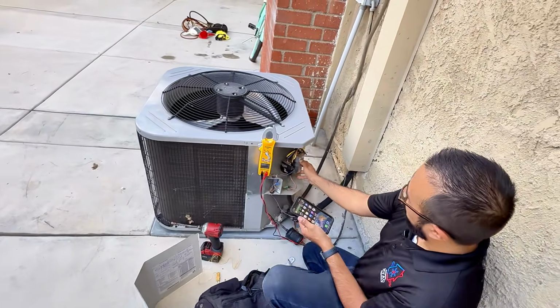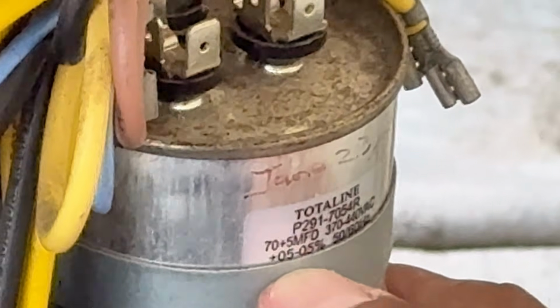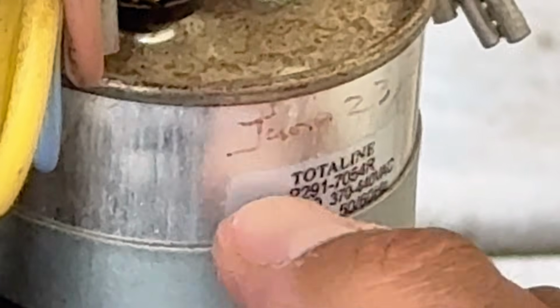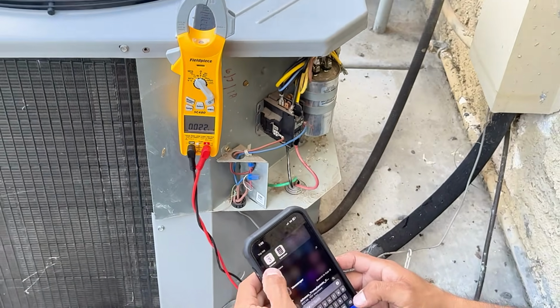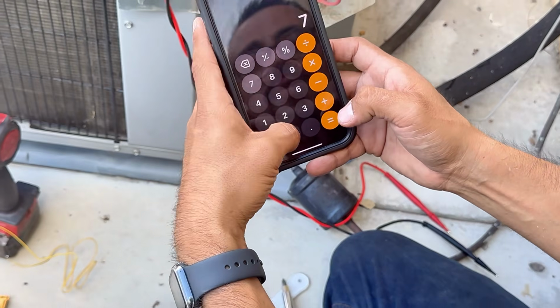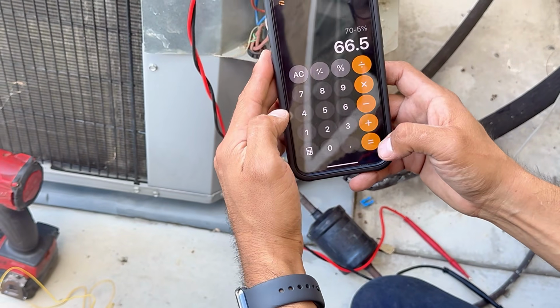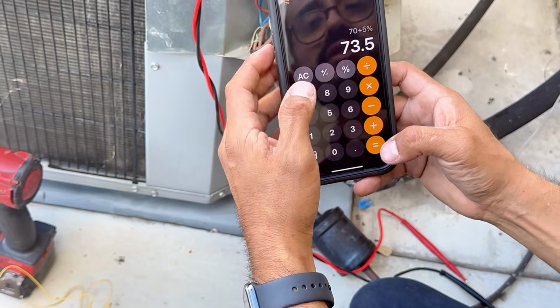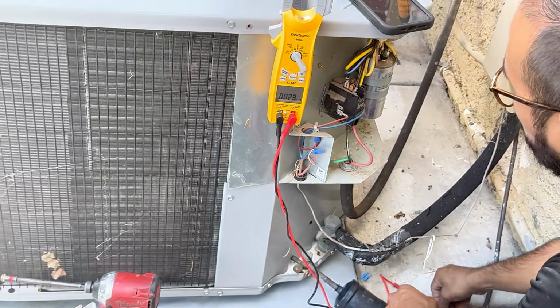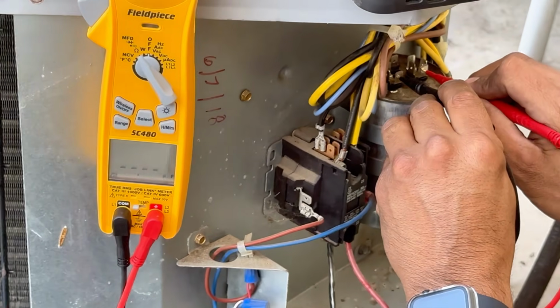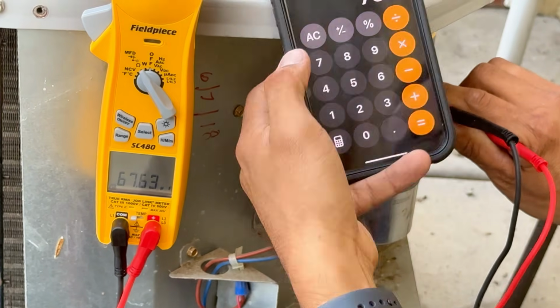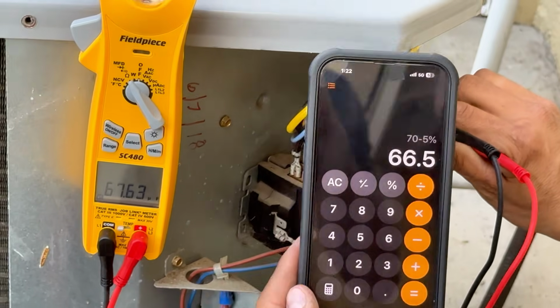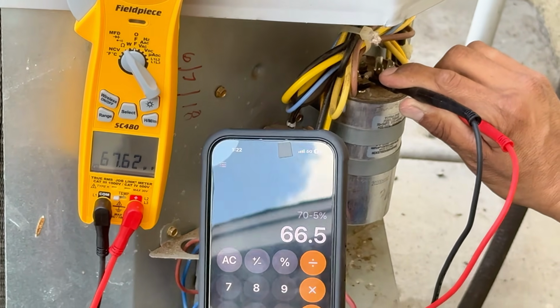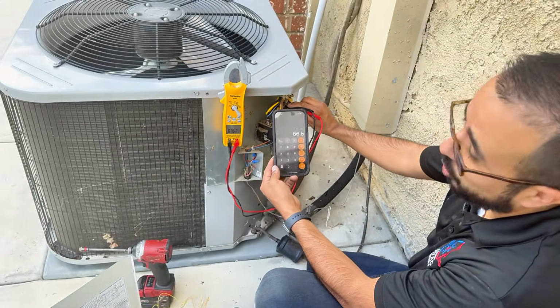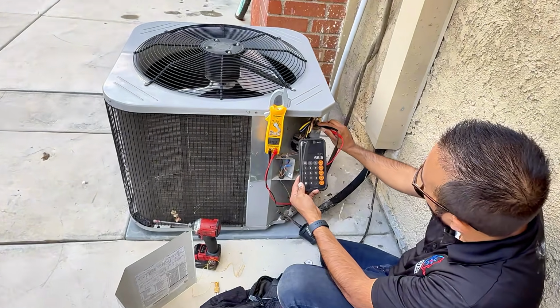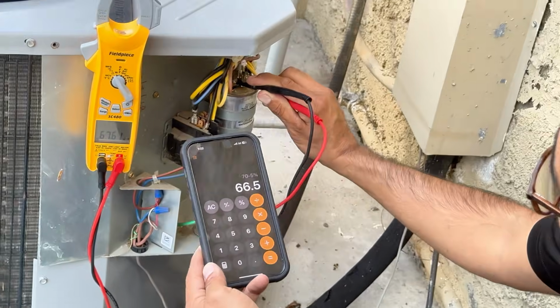Let's zoom in on that right there, 70 plus 5, you see the bottom, guys? Plus or minus 5%, 70 plus or minus 5%. So I'm going to my calculator: 70 minus 5% is 66.5, 70 plus 5% is 73.5. That's the range, 66.5 to 73.5, and I was at, yep, within range. The lowest I can go is 66.5, and I'm at 67.62, so it's getting weaker but still within range. I don't necessarily have to recommend it as a part to replace, but maybe before summer of next year I probably would replace it.